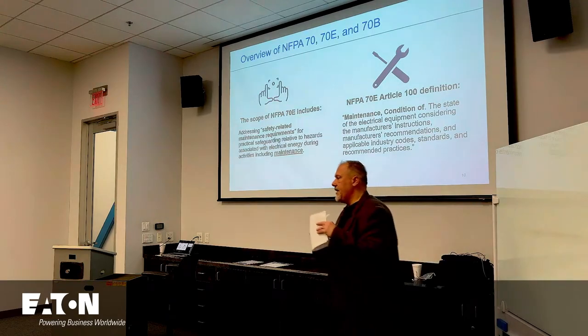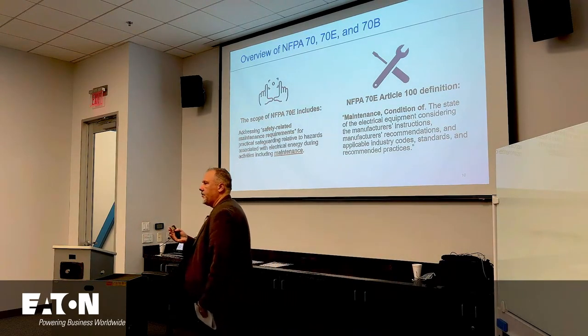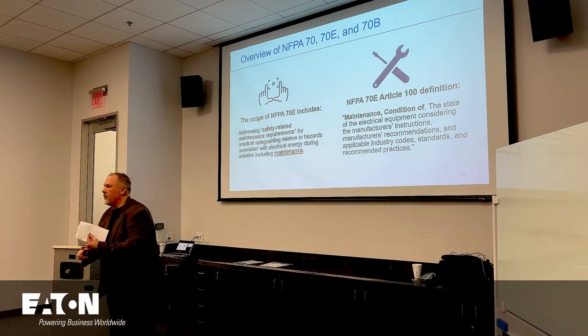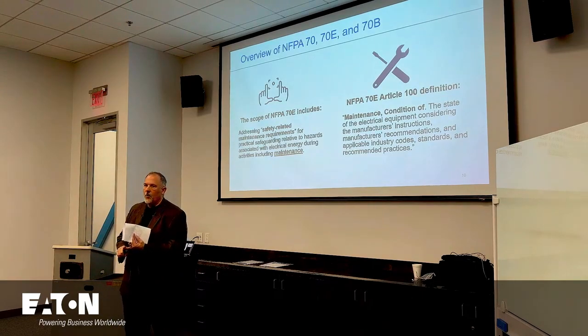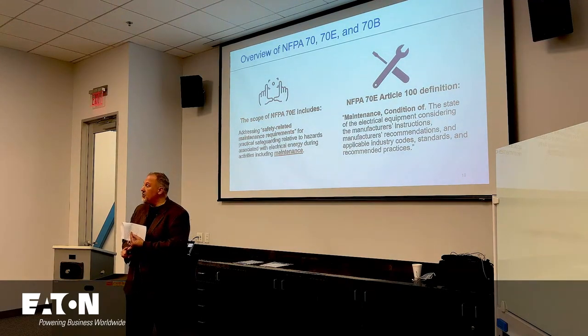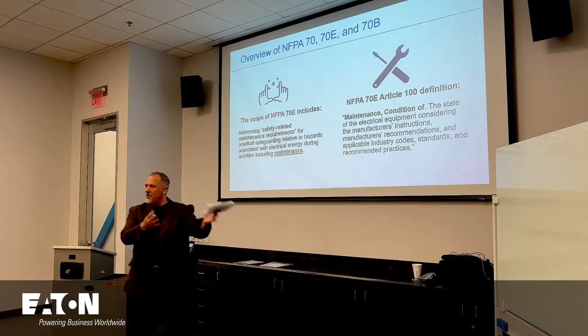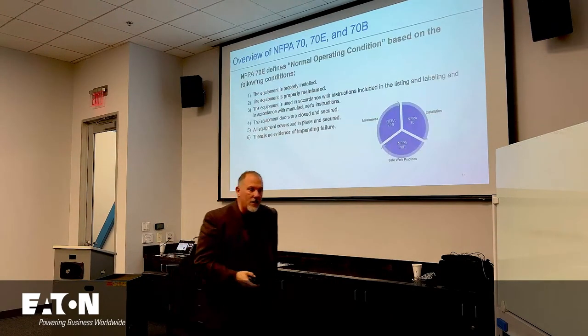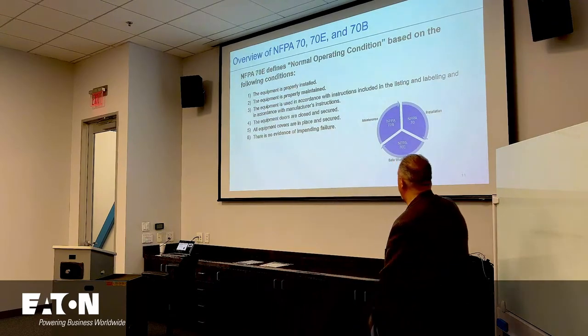If you look at 70E again, it'll tell you what we use 70E for. We dress with PPE. We're relying on equipment to do its job. And if the equipment is not maintained, it's not going to do its job, or may not. You can't ascertain whether it will or not because you haven't maintained it. So your 70E safe work practices plan is null and void because you're basing it on a system that's not maintained. Very important to maintain the system.